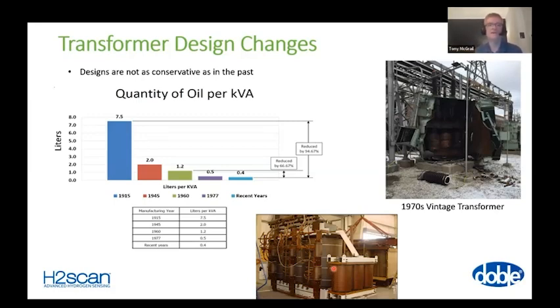So they are complex items, and looking at the size of that transformer, if you drop a small piece of copper, just a small piece of a penny, into that transformer, you can kill it without any problem at all, because there are certain places where it can go and it will just cause problems with the electric fields. So they are extremely strong under pressure, but they're extremely, what's the best word for it? Susceptible to problems as well. Yeah, delicate situation, right? Delicate, yes. Take care of them.